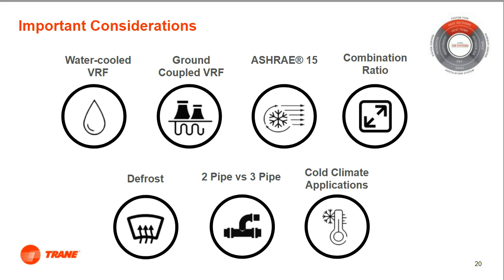And lastly, cold climate operations can be tricky with VRF systems. Some manufacturers have condensing units which can provide heating down or below 0 degrees Fahrenheit or -17 Celsius. Also, low ambient accessories can be provided to offset the low temperature applications as seen in many parts of the country.